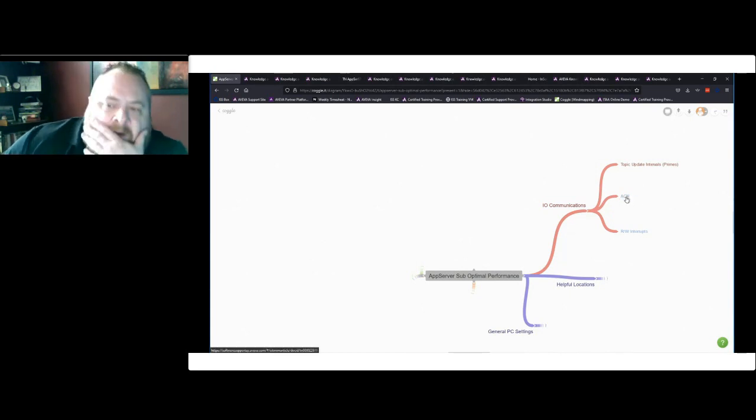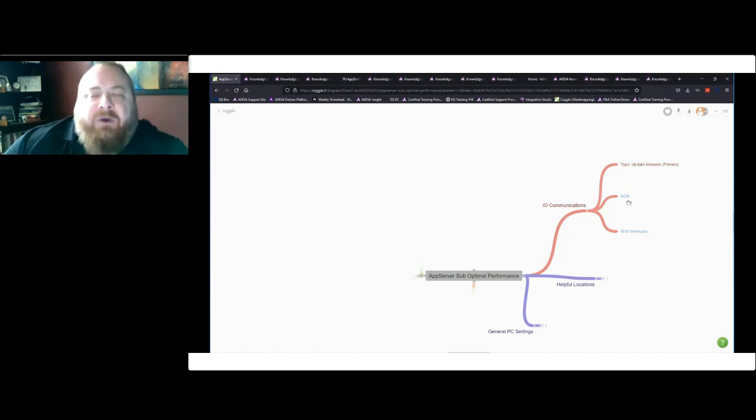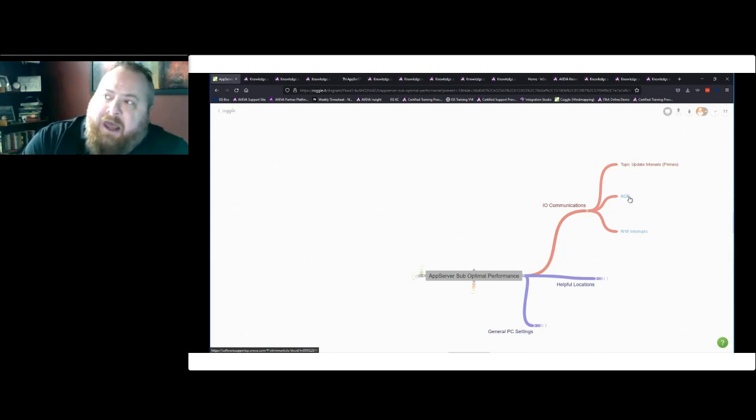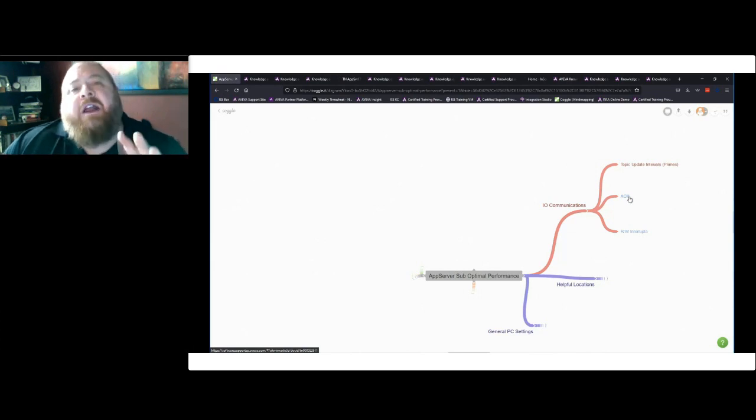And then, so this was a neat little feature that I don't remember exactly which version it brought out, but it was called Advanced Communication Management. And so you may or may not be aware that prior to Advanced Communication Management, all topics in AppServer were set to advise all the time, which basically means it added tremendous potential load on your network. And so if you think back to the InTouch days, an access name can be either set for advise only active items or advise all items. And so that was, to AppServer, what that behavior was for InTouch.